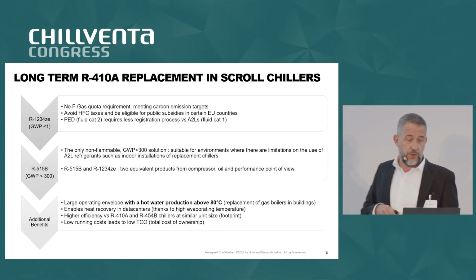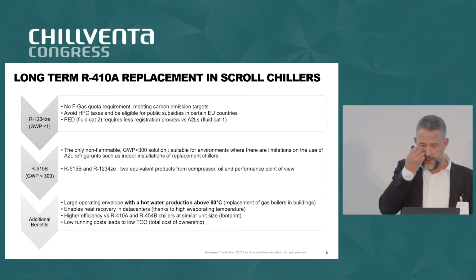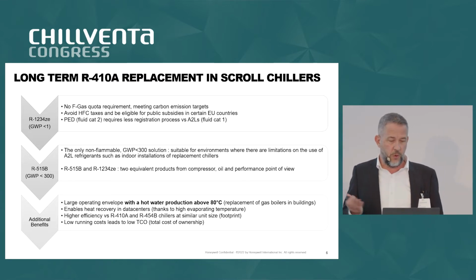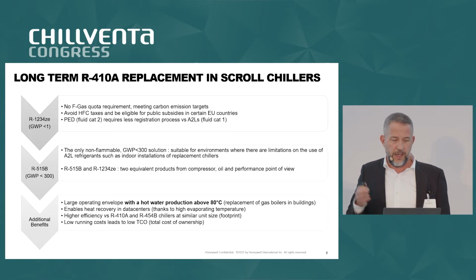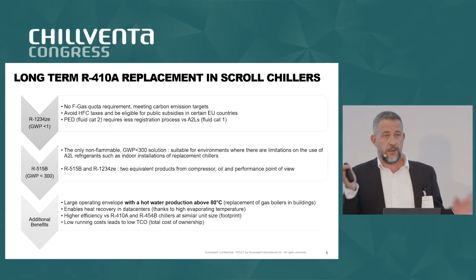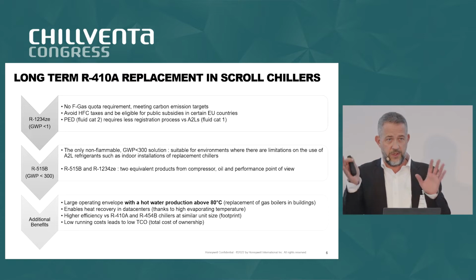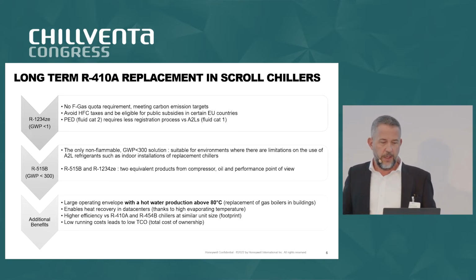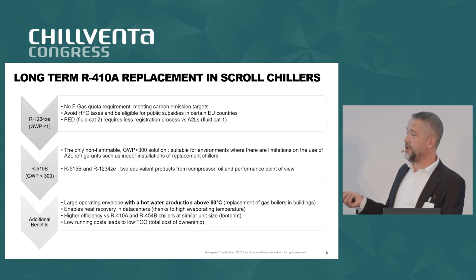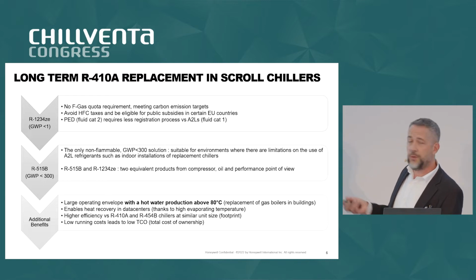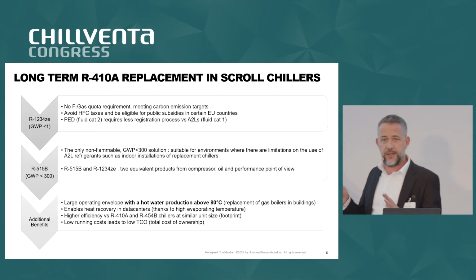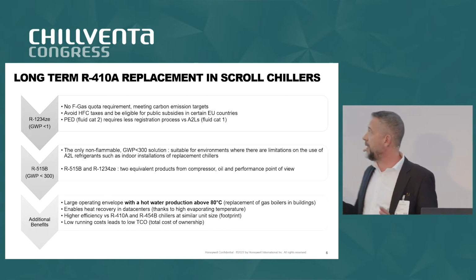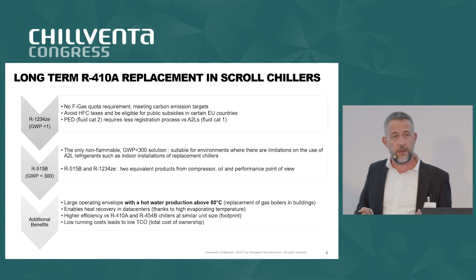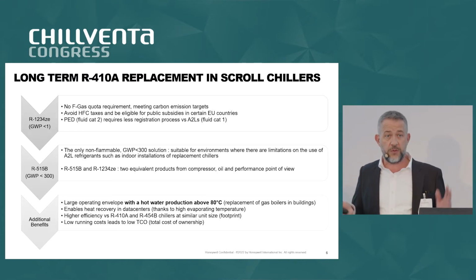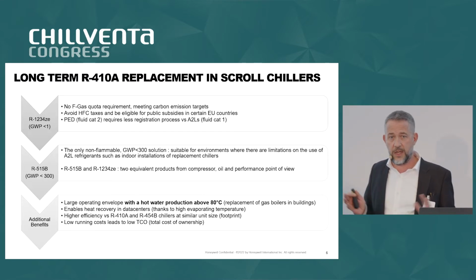515B is today the only non-flammable option with a low GWP below 300. And the interest, as I said, is the same technology using the two refrigerants, okay? Another additional benefit, and you will see it, is the possibility to increase the water temperature compared to R-410A. R-410A was stuck at 60, 65 at best. Now we can go very easily to above 80, which is a real breakthrough as well in this kind of platform.